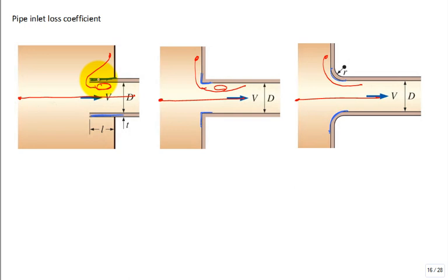That's what I'm looking at, table 8.4. And that loss coefficient for this case would be around 0.8. Don't take that to the bank to three significant digits. This is fluid mechanics. You know, these loss coefficients depend a lot on if you have it tilted a little bit, how far in, what does the edge and the thickness of the wall look like. But if you wanted a number, run with 0.8. It gets you in the ballpark.